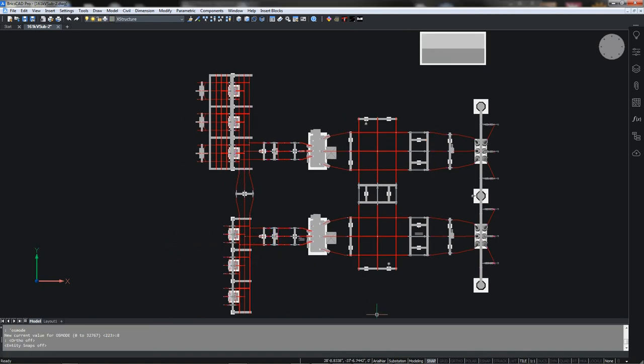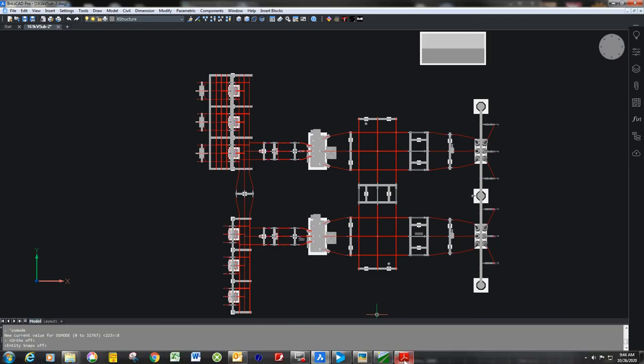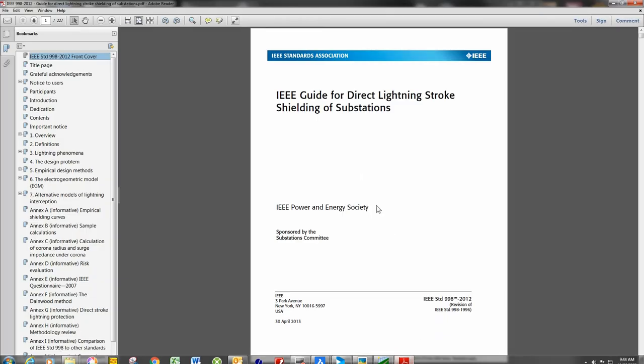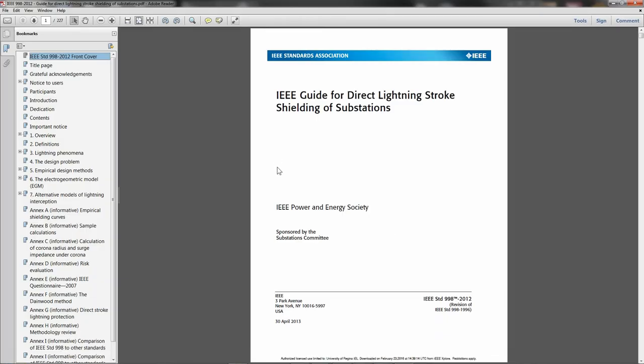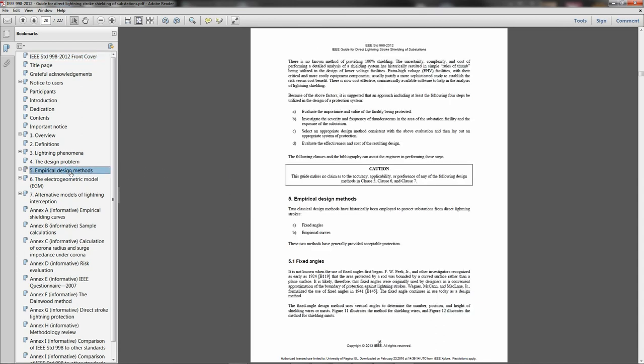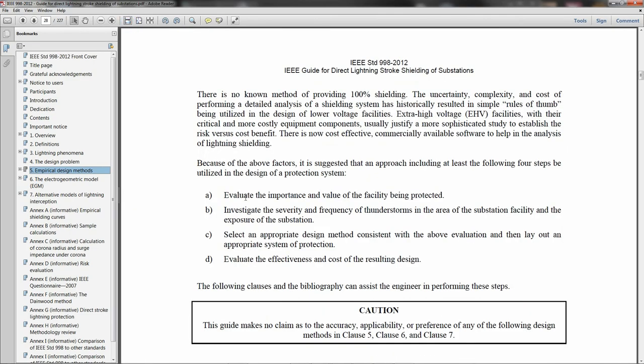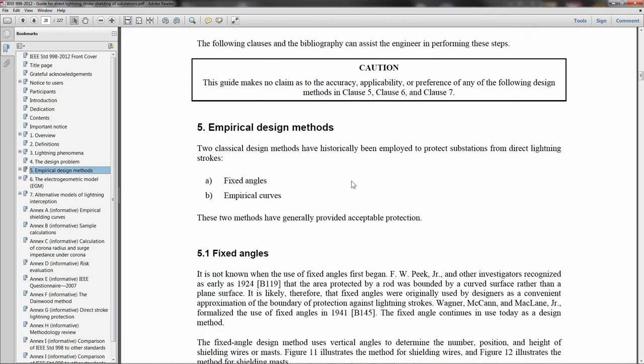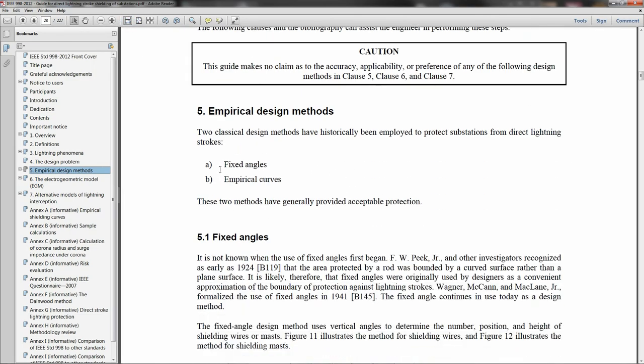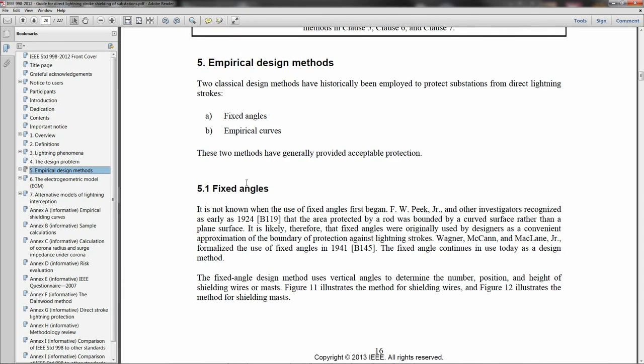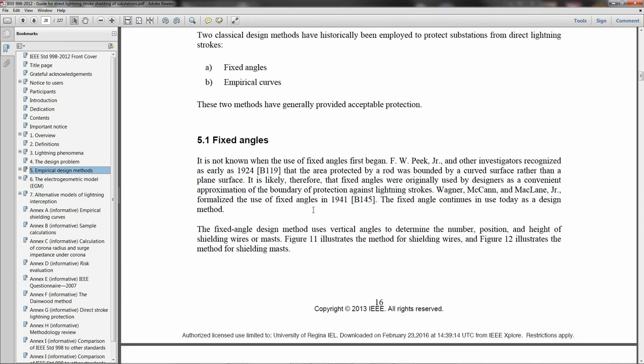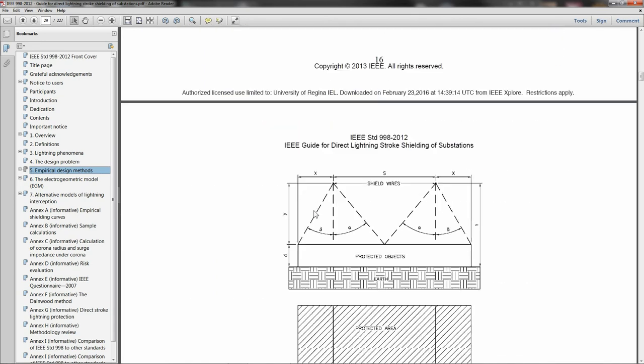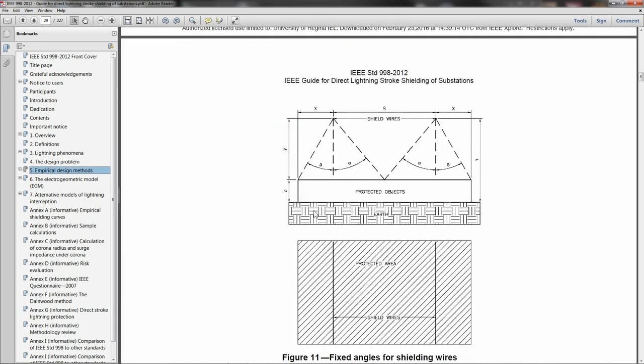IEEE standard 998 presents their guide for substation lightning protection. They present several methods but today we're going to be looking at specifically one of the empirical design methods. They use the fixed angle method and empirical curves which are derived from actual field values. We're going to be looking specifically at the fixed angle method.